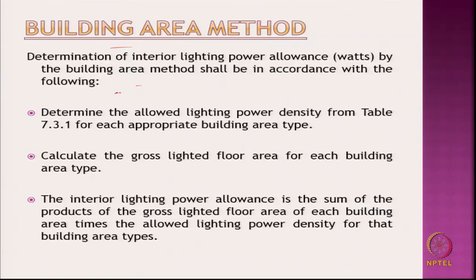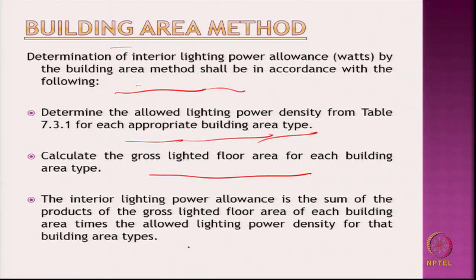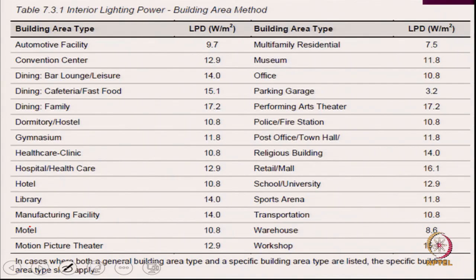Now, here, through the building area method, the total interior lighting per unit area is given in a table. For example, for a classroom, for a given floor area, how many watts is given in tabular form. One can calculate the gross lighted floor area of each building, and the interior lighting power allowance is the sum of the products of the gross lighted floor area of each building times the allowed lighting power density for the building area. So, basically it is telling you how to find the quantity of lighting required, and this is given in tabular form. So, from the building area method you can find out what lighting is required, right. Lighting power demand values are given for an automotive facility, convention center, museum. So, per unit area, watt per meter square, how much lighting is required is given.